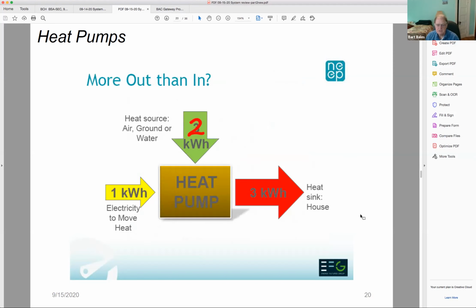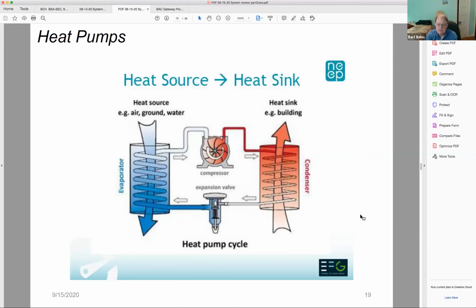It counts on, go back please. This counts on the evaporator side. It counts on a lot of free air to move past this coil. So it's very important to leave free space around condensers. You can't enclose them. You can't put pretty things around them unless you do it from a good distance so that there is good air movement.